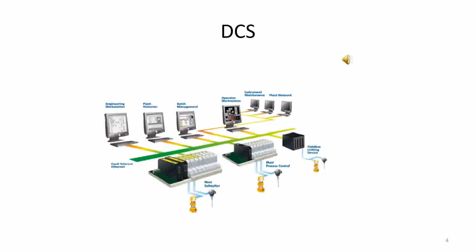The real DCS has controllers in the field, avoiding multi-cables and two cabinets, and has a communication network to access workstations. It is a real distributed control system with controllers in the field in small control rooms of every unit without personnel. Operators are situated in a central control room connected with field instrumentation and controllers by Ethernet network. In case of failure of Ethernet network, plant continues to be operated from the field without interruption.